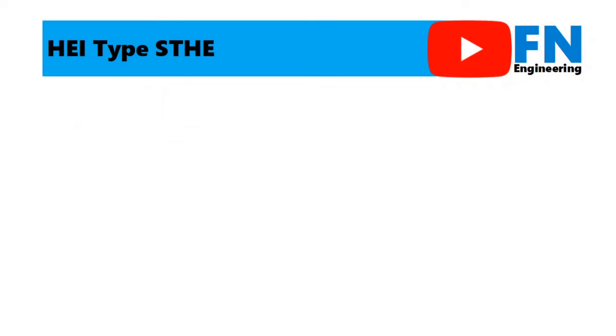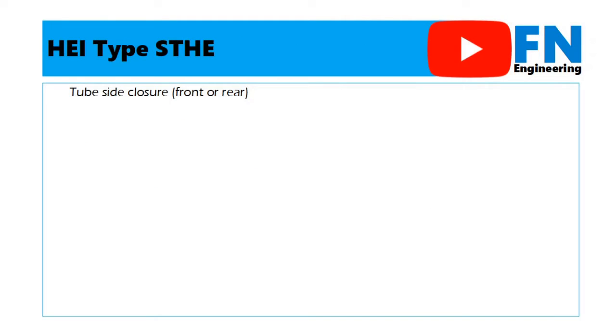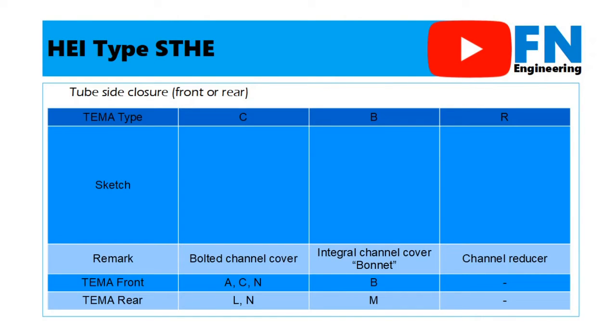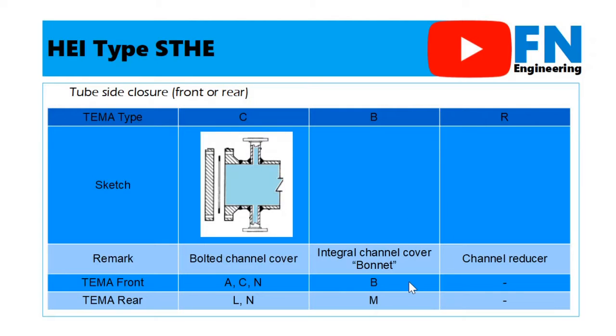First of all, tube side closure. It can be in the front head or rear head. There are 3 types of closure. They are type C, type B, and type R. Type C is a bolted channel cover. If we see the TEMA type, it is similar to TEMA type A, C, or N in the front head, and type L or N in the rear head.